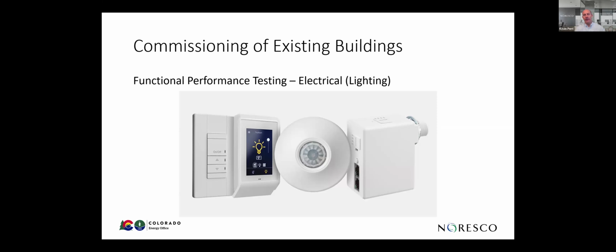Sampling says by code 10% and no fewer than 1 of each combination. So you might have a dual type occupancy sensor. You might have 10 of those and 10 of just single occupancy sensors. So then you have to do at least 1 of each. You can always test more, and I don't think any code official will ding you for testing more.